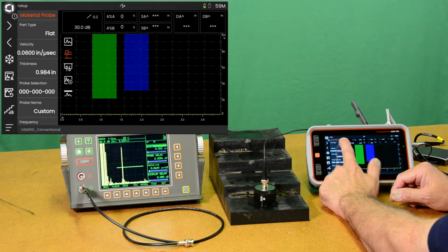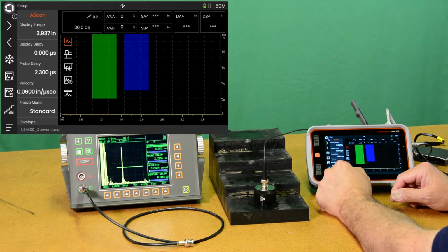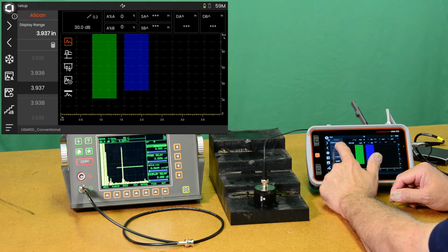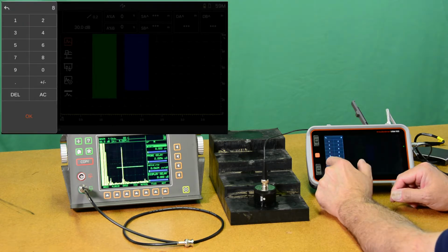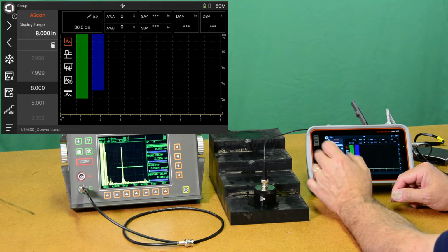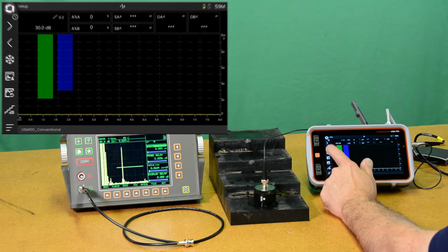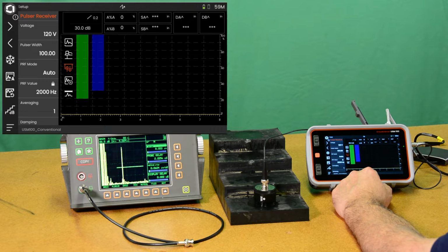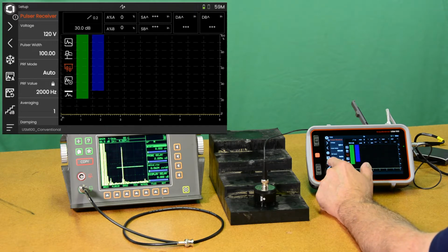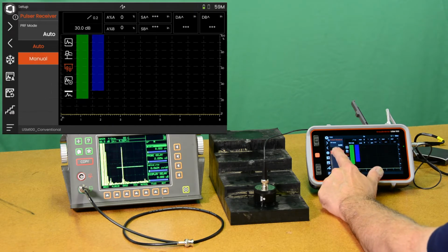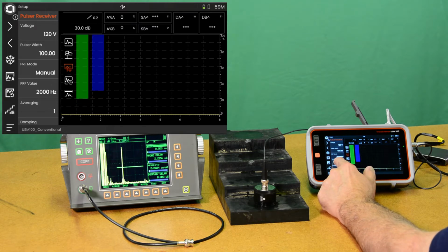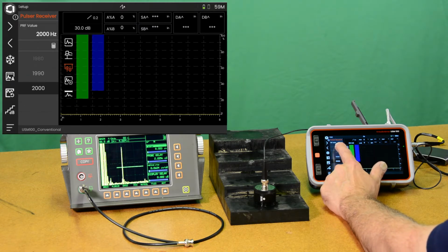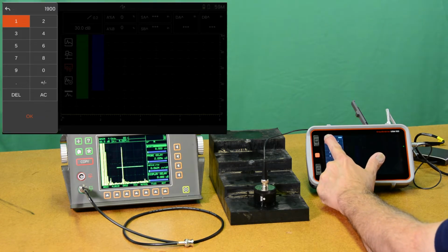Then we're going to go to our A-scan menu. And we're going to tell it that we want 8 inches of display range. That'll be nice for looking at the various steps in the block. Okay, we'll go to the pulser receiver menu. And the first thing we're going to do is go to manual PRF mode. We want to set our rep rate low because we're using a very wide pulser. I can scroll down, or we're just going to go right to 100 hertz.